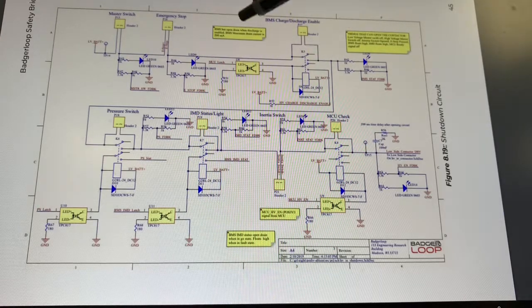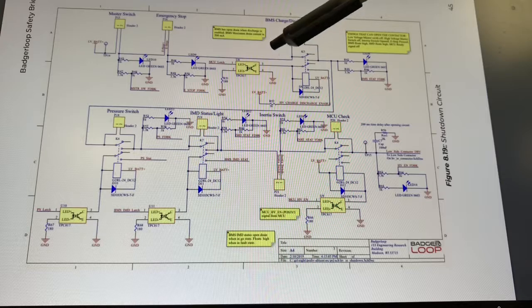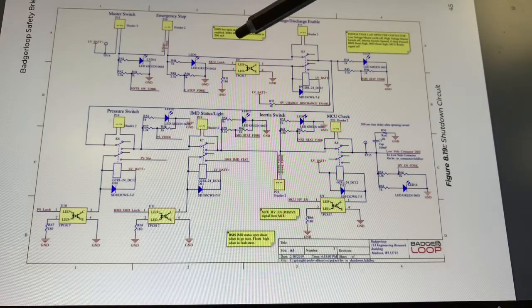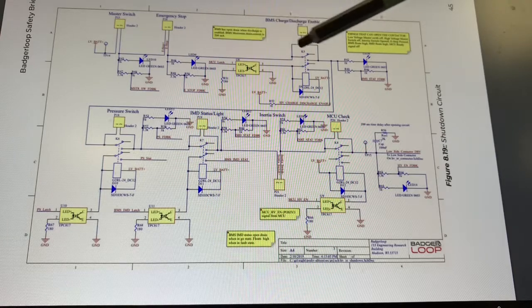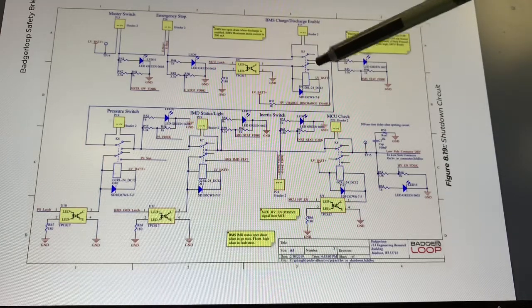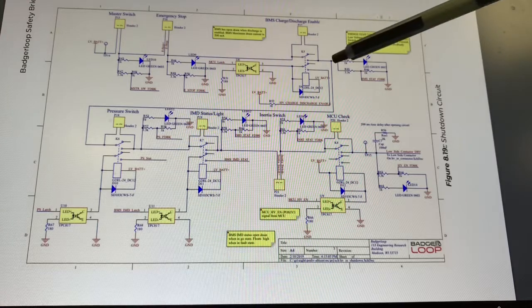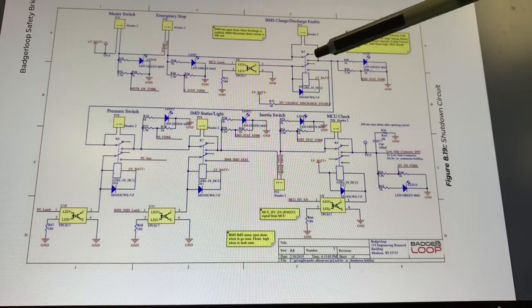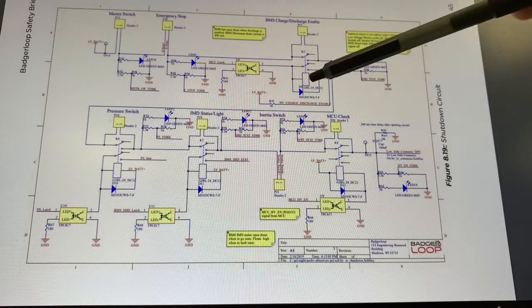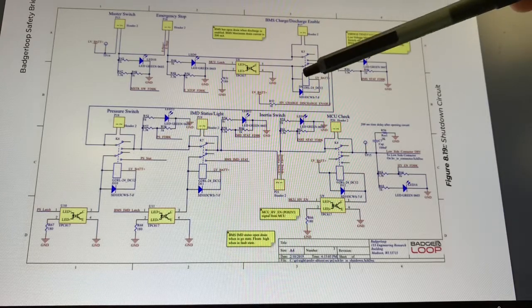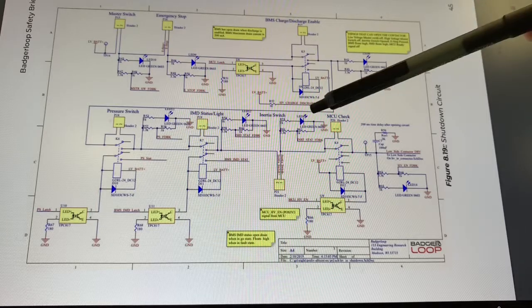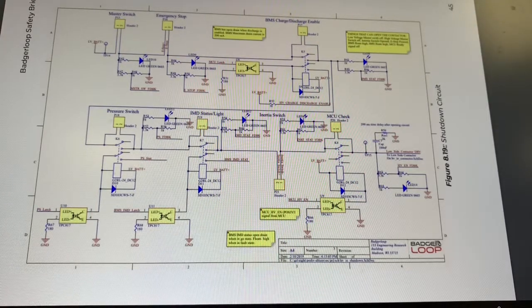Also on this part of the circuit, we designed a latching feature that must be applied from our microcontroller, or the BeagleBone in our case. It's called MCU latch. Once the MCU sends a signal, the relays will close, and if the battery management system is in an okay state, they will remain closed. If not, once the signal is unapplied, it'll open again and the contactor will not be driven.